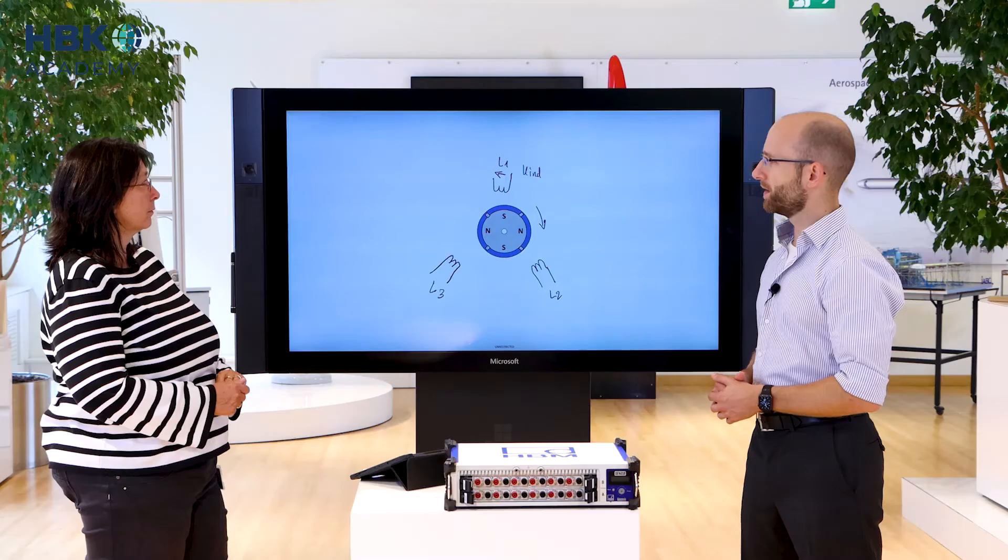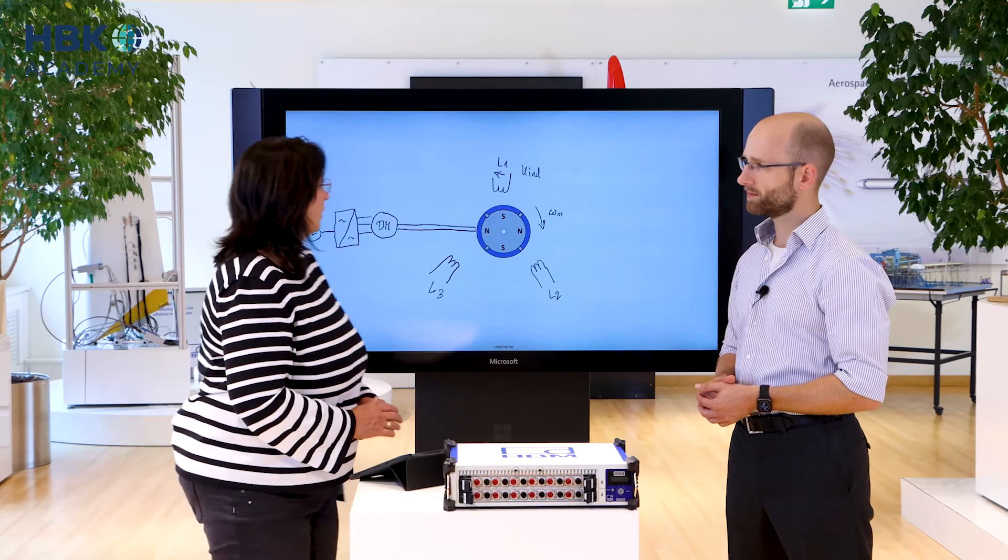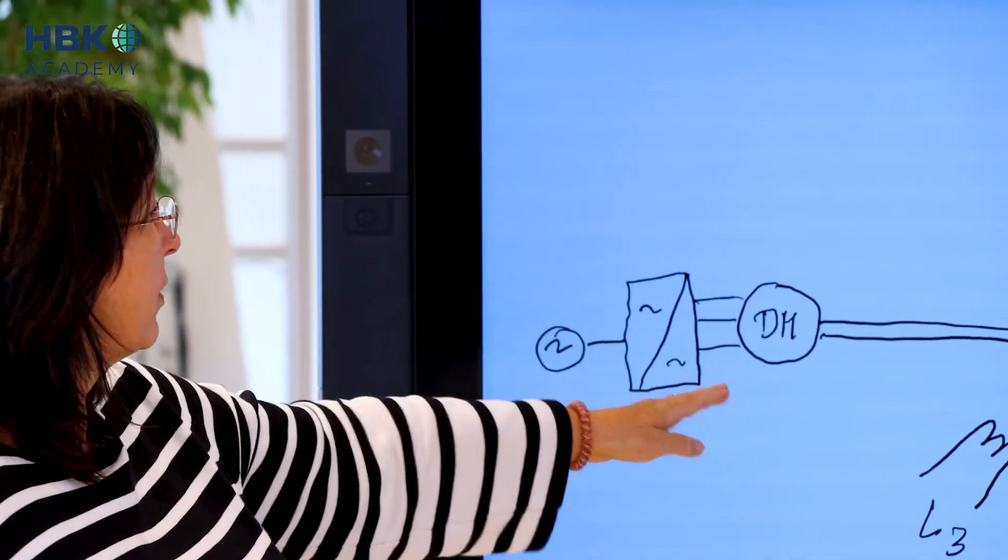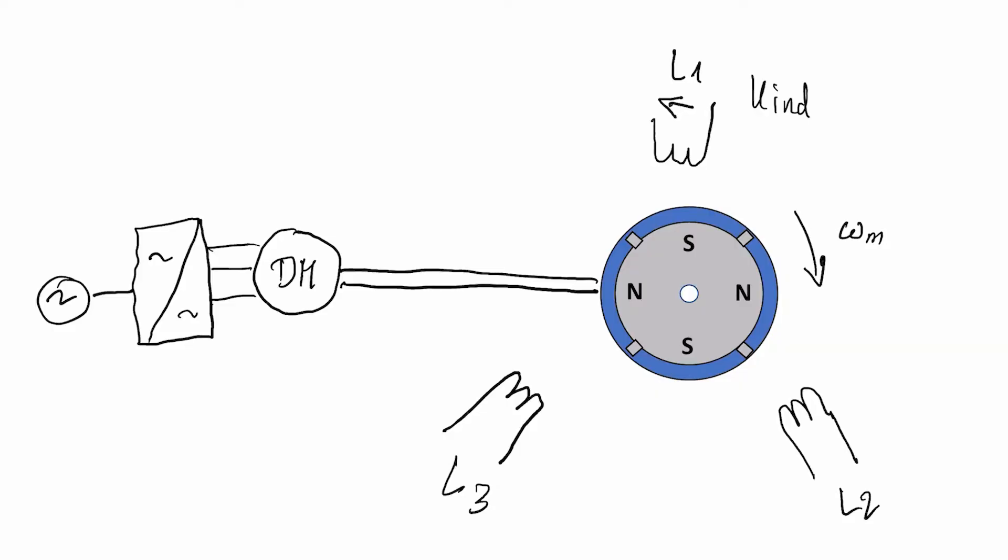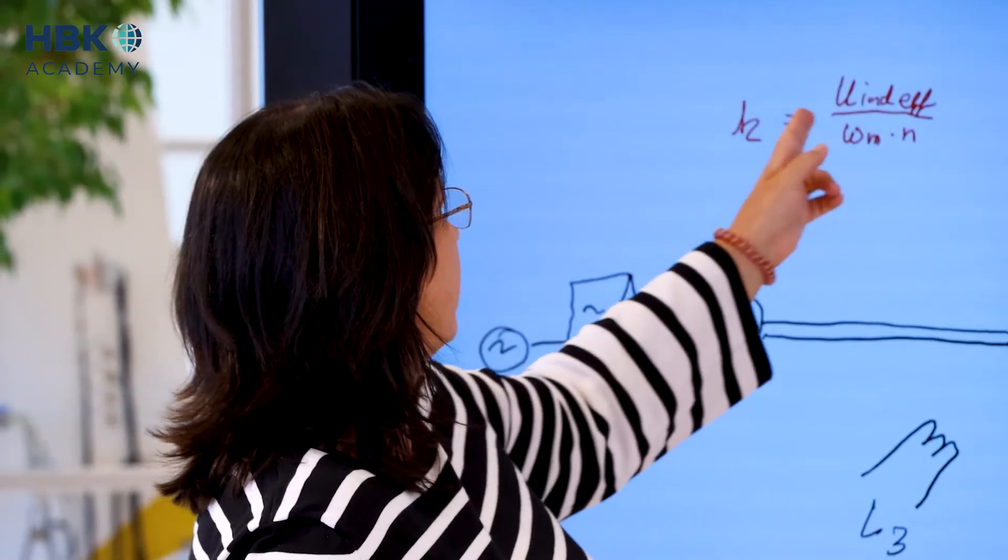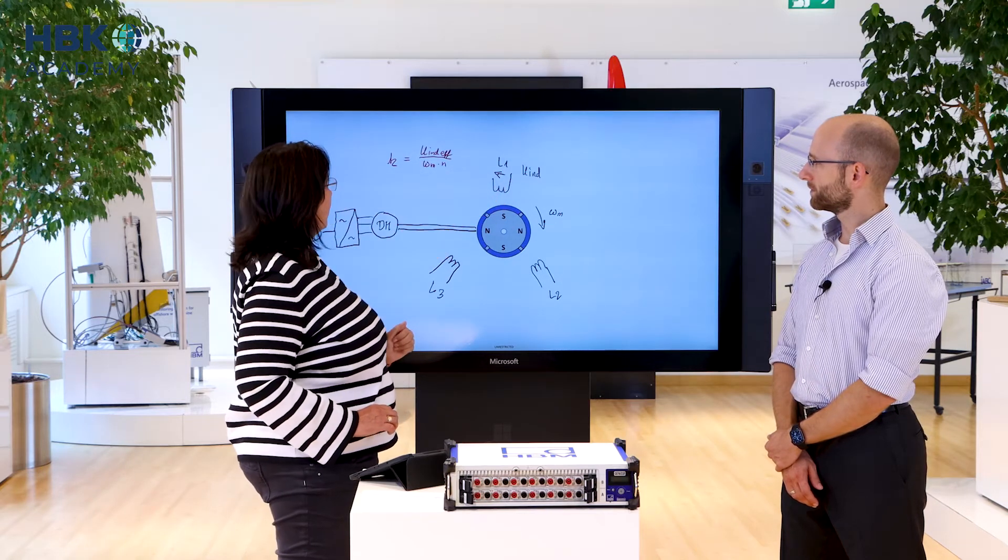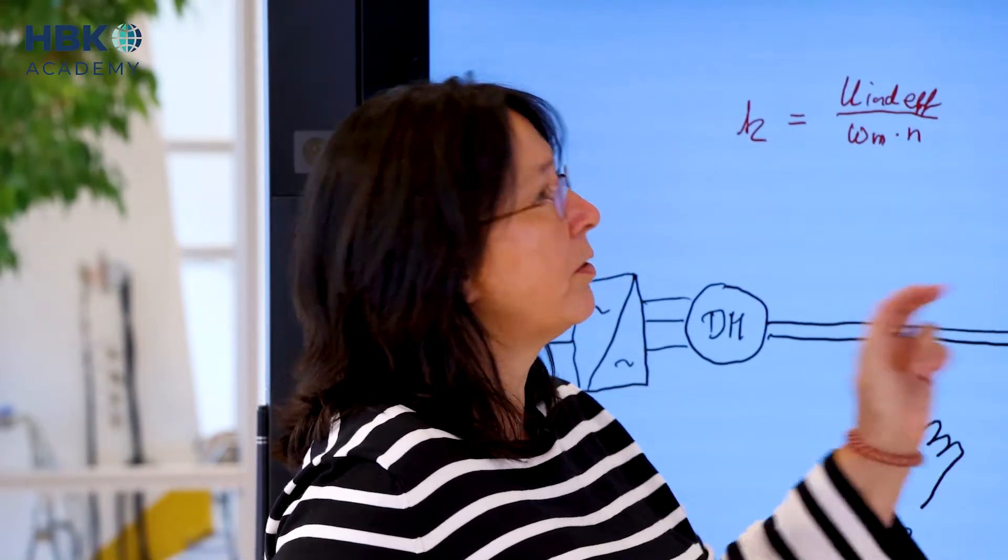And how is the back EMF test normally done? In the classical way this back EMF test is done with a second motor that drives this rotor at a constant rotational speed. And for the control of the second motor we need also an inverter and an additional power source. The goal is to calculate a constant and this constant is the RMS voltage that we can then measure within each phase divided by the number of pole pairs and the rotational speed.